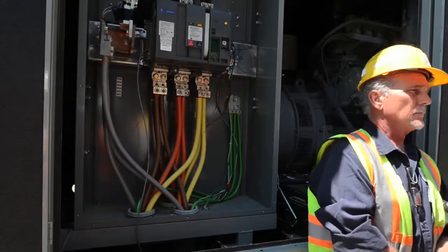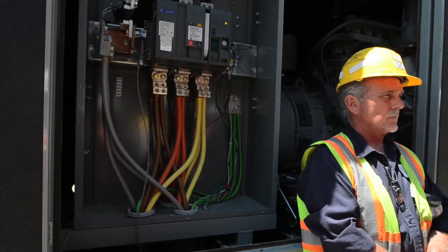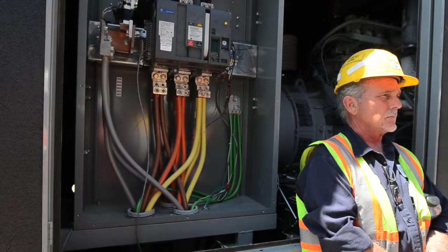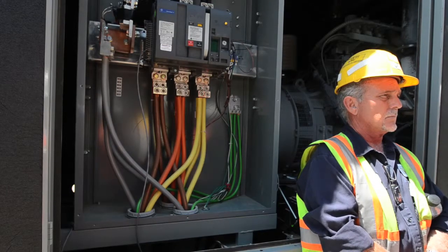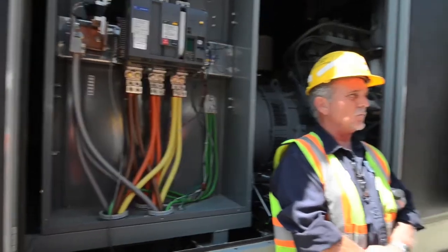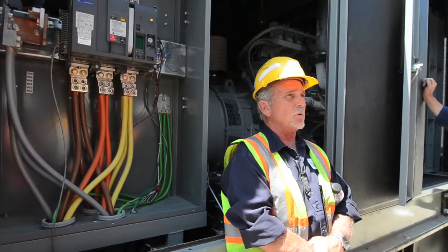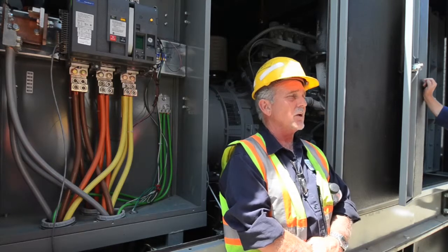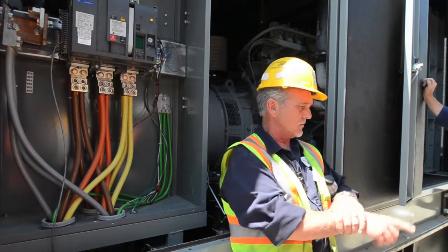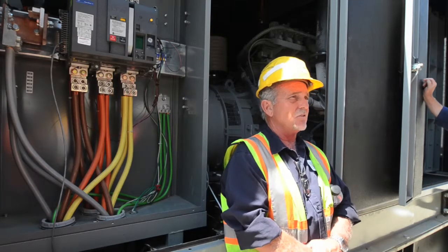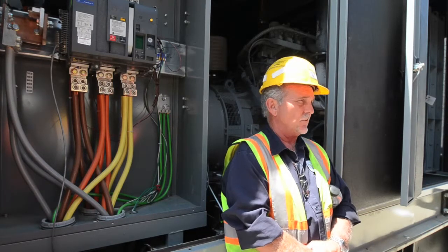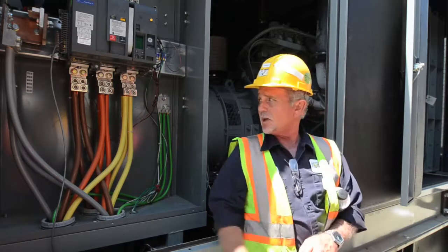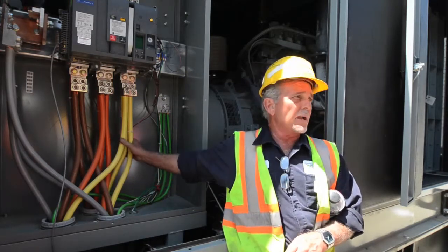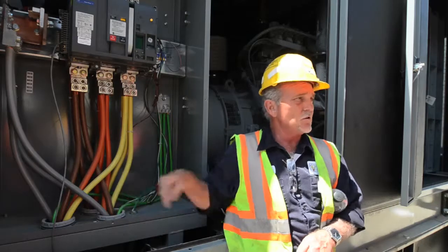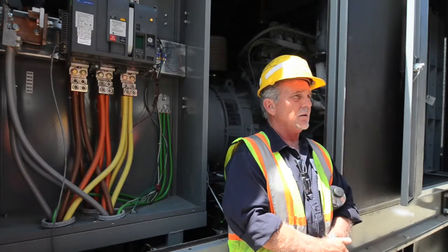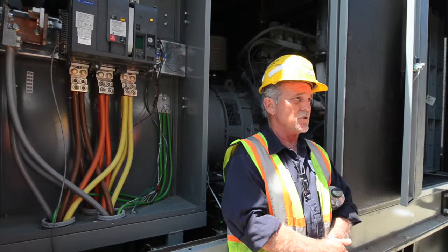In the event that the gensets went down and they wanted to bring in auxiliary gensets to hook up, do they hook them up directly here? Or they can hook them up at the, well, realistically what would happen is if you brought in an emergency genset, the ideal location to tie it in would be the emergency bus down in the lower room. If you're going to bring in another generator that's compatible to one of these, another 650, then what you could do is you could actually go ahead and they could pull these wires back and attach to it and feed this because it goes to the emergency bus. But in the event of doing that, you have to disable both of these generators.